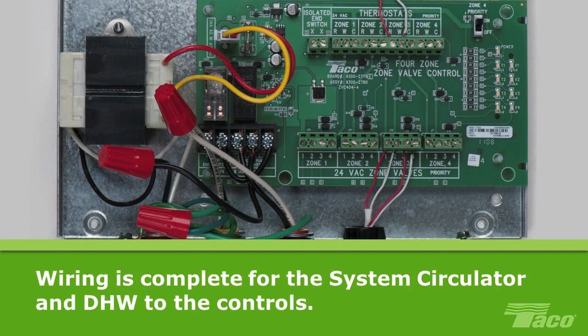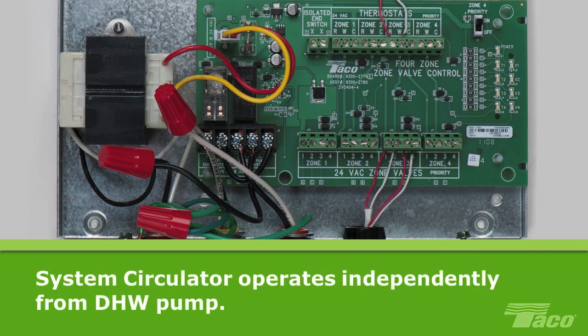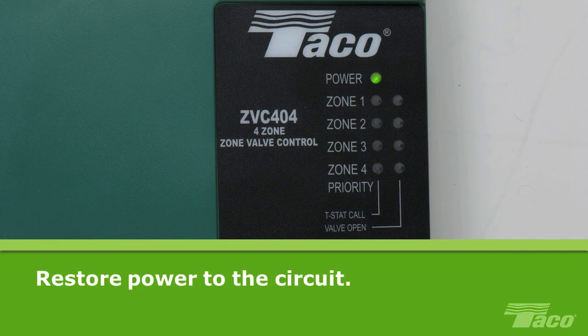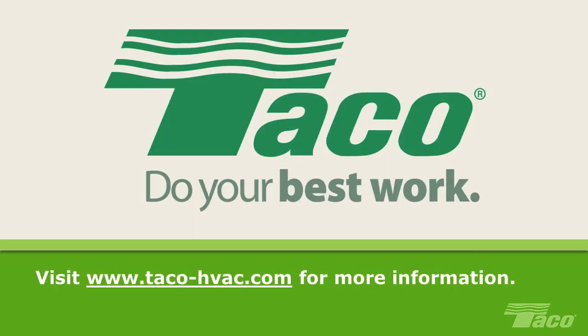That completes all the wiring of the system circulator and domestic hot water circulator to the controls. When wired for domestic hot water in this configuration, only the DHW pump will respond to a call for hot water. The system circulator operates independently from the DHW pump — there is no power to the system circulator when there is a call for hot water. Now you may restore power to the control. The green LED indicator light will glow, indicating that the power is connected. The green LED should always be ON as long as there is power to the board. For additional resources, product information, and comprehensive tech support, please visit Taco on the web at www.taco-hvac.com.